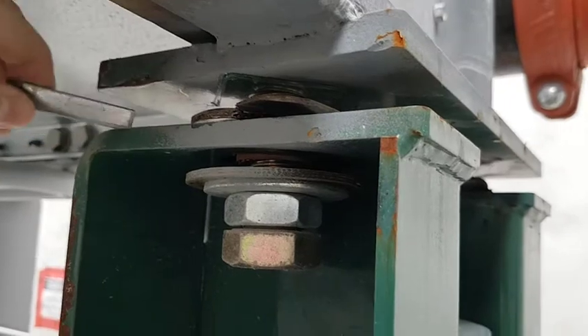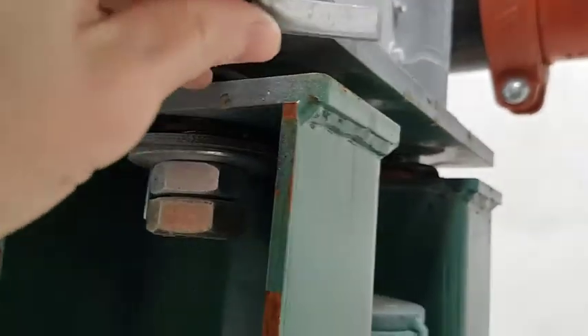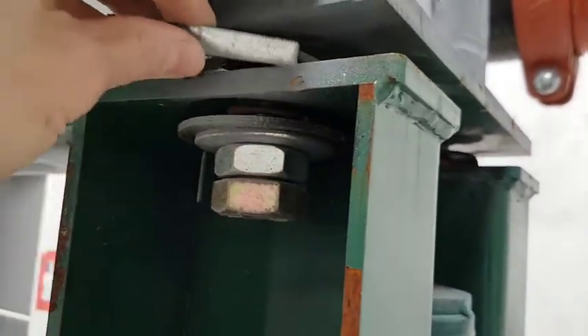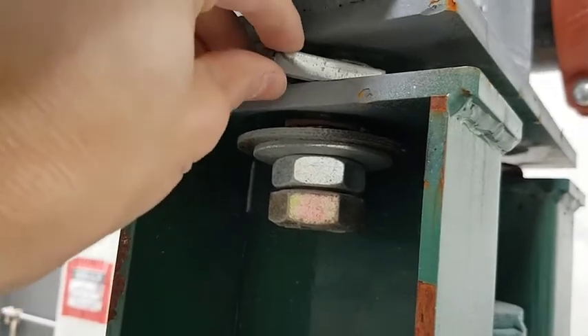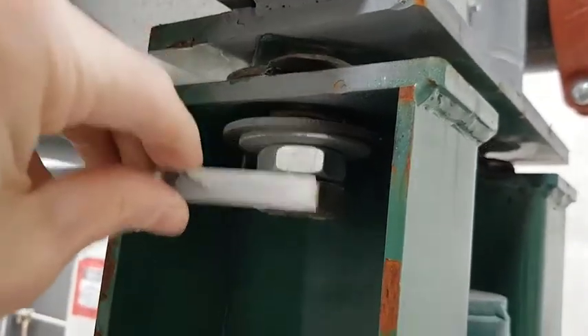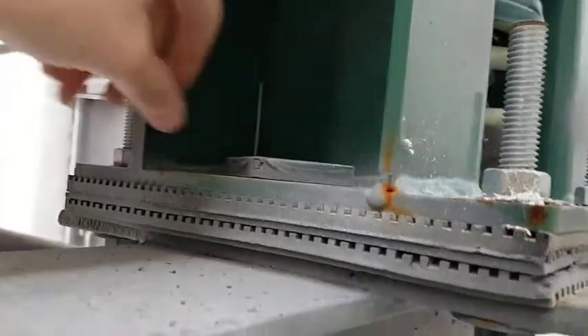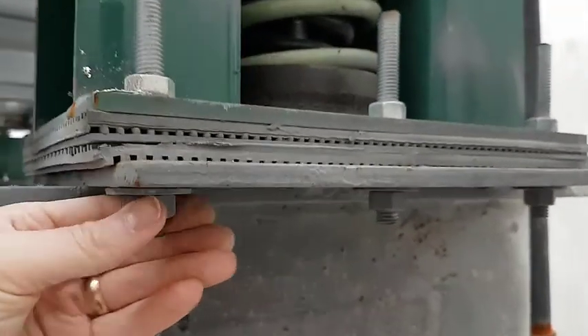We can see how much extra room there is in the gap, probably as a result of the isolators being adjusted before the tower was brought up to its operating weight. The spacer should have been positioned like this, next to instead of on the rubber washer. These makeshift bolts appear to be adequately tightened on this isolator, so we know it's attached to structure.